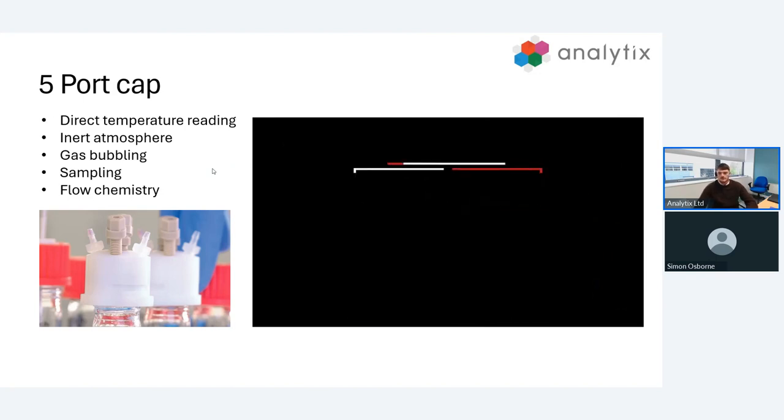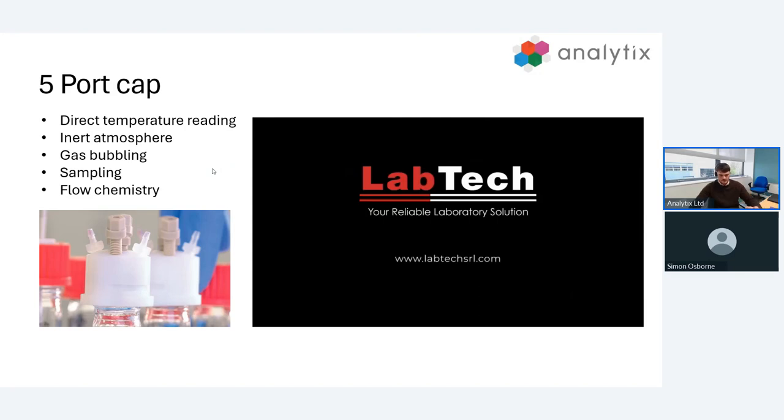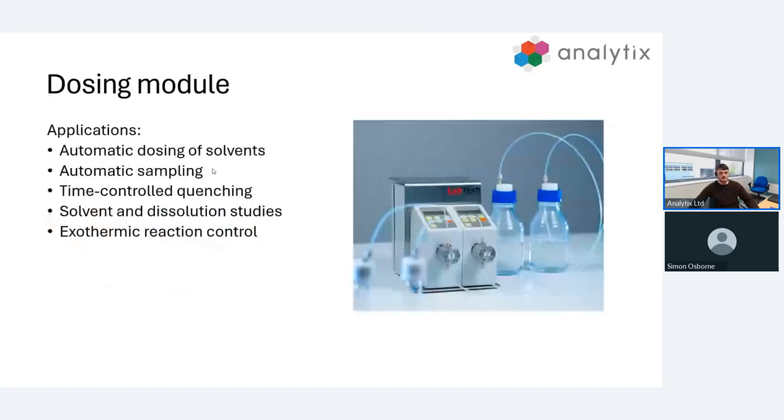I hope that gave you a better picture of the system and potential uses of the five port cap. This is our dosing module. This is an automated dosing station that is programmable within the software to dose at specific time points. It's automated dosing and sampling. We can do this for time controlled quenching, solvent and dissolution studies, as well as exothermic reaction control.